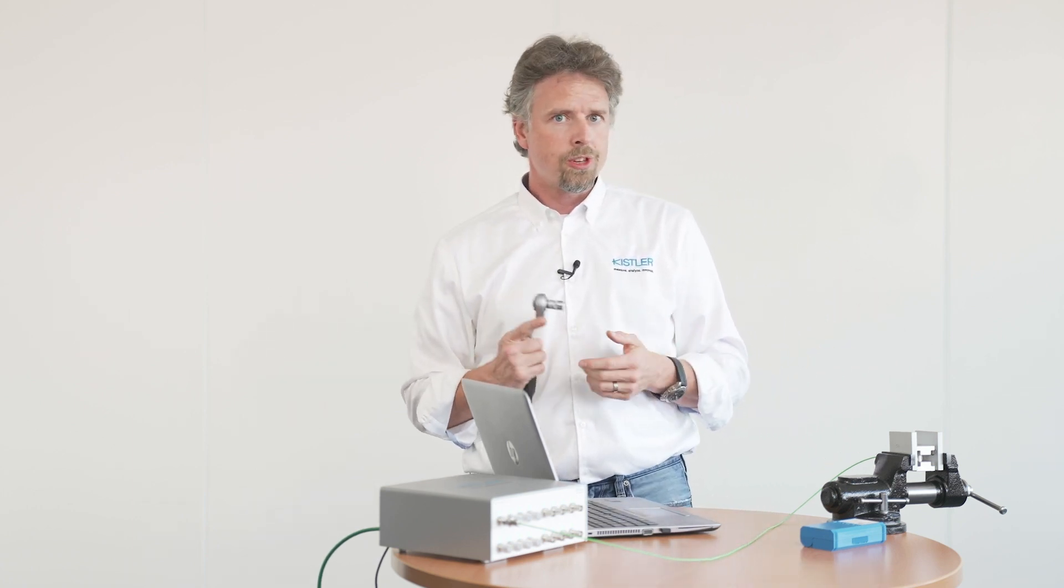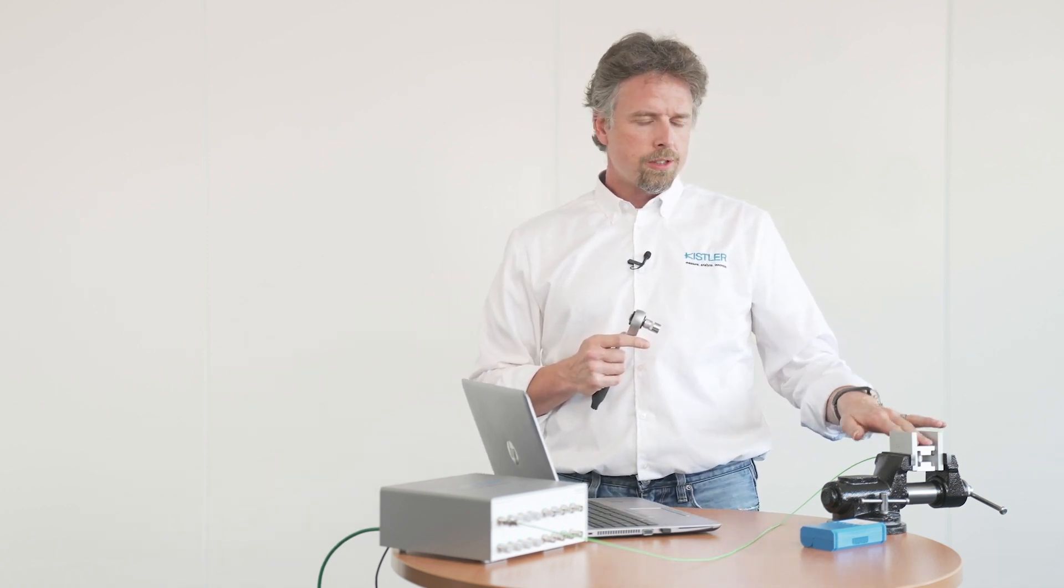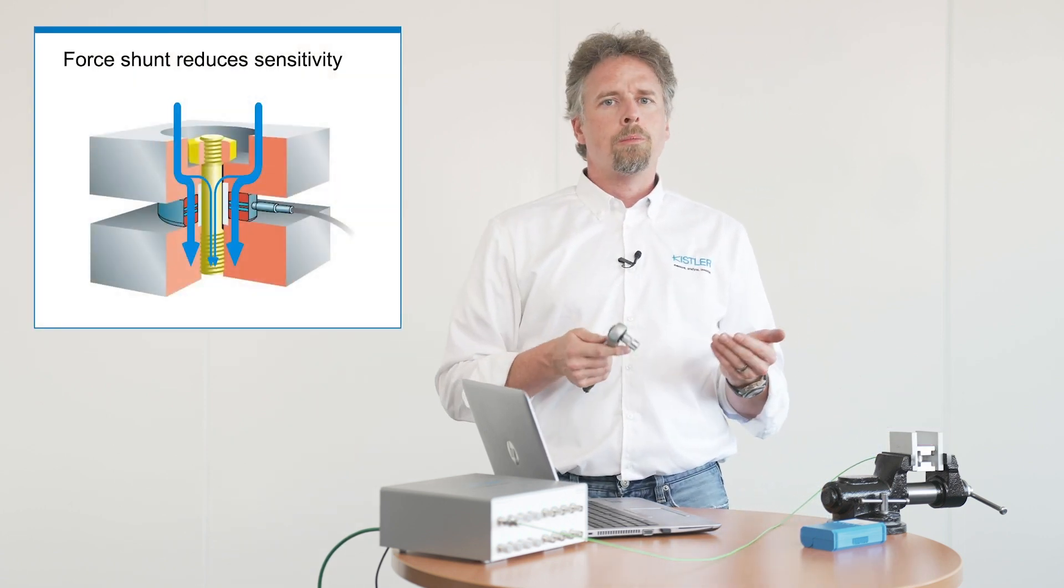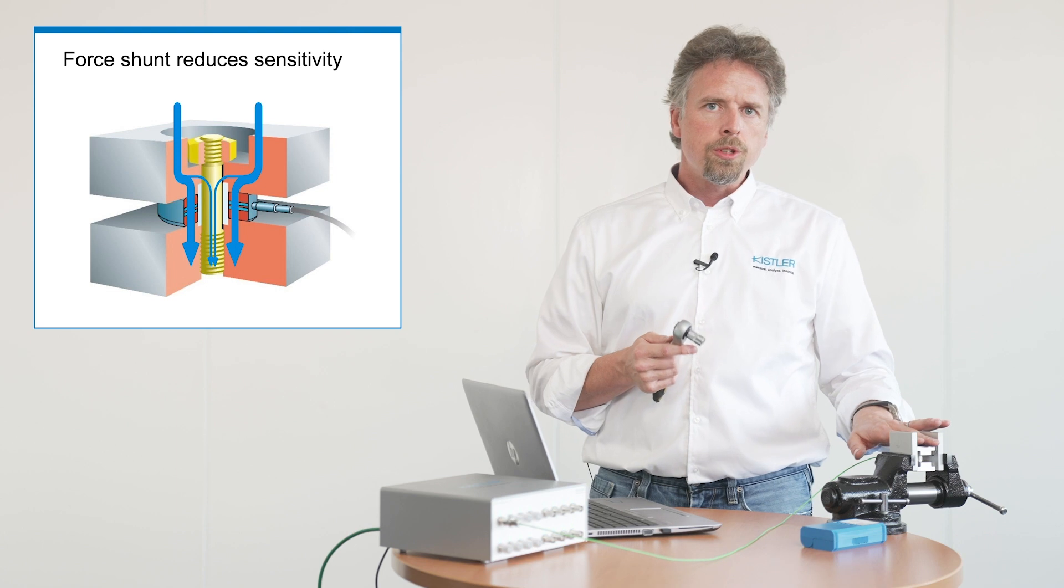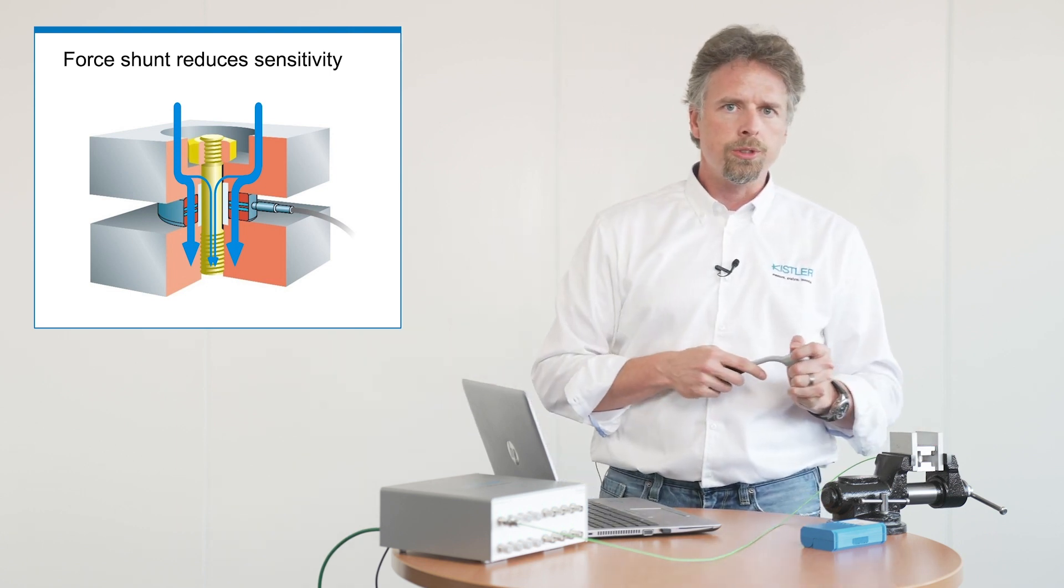Except for one thing which is really important. And with the bolt that you applied here into your structure, you have a force shunt. That means your sensitivity is reduced by 7% to 8% depending on the bolt you are using.